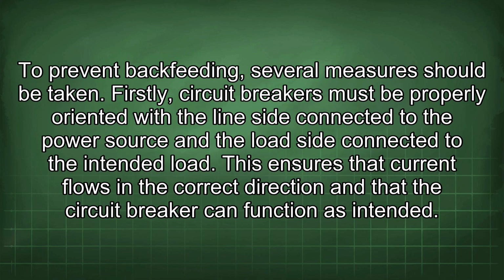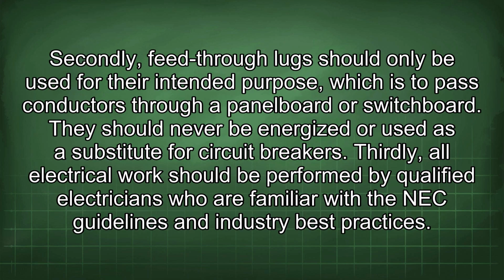To prevent backfeeding, several measures should be taken. Firstly, circuit breakers must be properly oriented with the line side connected to the power source and the load side connected to the intended load. This ensures that current flows in the correct direction and that the circuit breaker can function as intended. Secondly, feed-through lugs should only be used for their intended purpose, which is to pass conductors through a panel board or switchboard. They should never be energized or used as a substitute for circuit breakers.